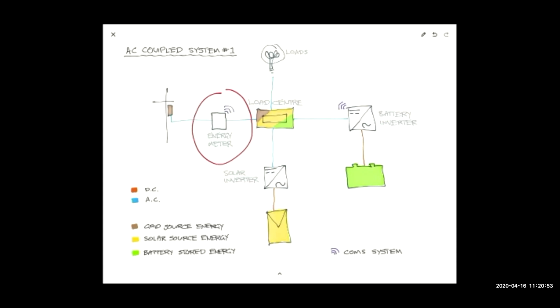Where I was going with this diagram is trying to show the importance of this energy meter. It allows communication of the flow of energy - is energy flowing out of the installation? It can see that because it's got its own current transformer and voltage reference. So if this PV system is pumping out 5 kilowatts, but the customer's loads are only 1 kilowatt, the difference will go out to the grid - we're spilling 4 kilowatts of renewable energy. Unless you're lucky enough to have a feed-in tariff higher than your purchase price, you don't want that to happen, particularly if you've got a battery inverter.